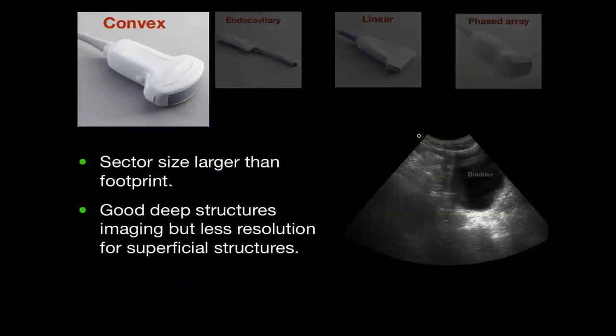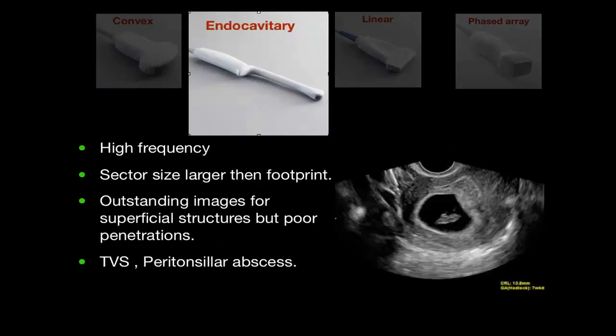The convex probe has a sector size larger than the footprint of the probe, and is excellent for abdominal or pelvic exams because of deeper penetration. The transvaginal is a high-frequency probe giving outstanding image quality, but without deep penetration — used mostly for transvaginal exams, though it can also be used intraorally, for example to see a peritonsillar abscess.